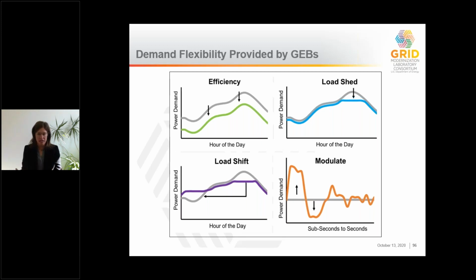Load shifting is similar—the time of day that we shift load can change. A great example is pre-cooling a building: running the chillers during off hours, maybe at night, so during the heat of the day the building isn't running chillers as high. That's just shifting the load to off-peak hours.